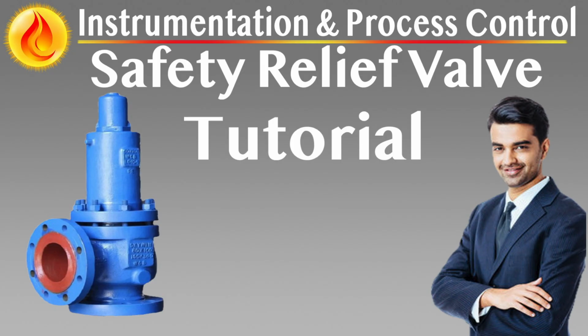Installation guidelines. Must be installed at the highest point of trapped liquid segments to ensure vapor or pressure accumulations vent correctly, prevent hydraulic lock or undetected overpressure, should discharge to a safe atmospheric drain or sealed liquid recovery system not connected to pressurized headers or flare systems. "Where freezing is a concern, the discharge line should be heat traced and insulated or designed with freeze-resistant drain traps."